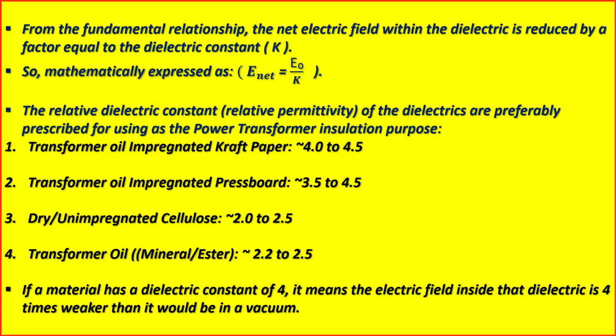It is very essential for designing a power transformer insulation system. Transformer oil impregnated kraft paper: the dielectric constant is 4 to 4.5. Transformer oil impregnated pressboard: 3.5 to 4.5. Dry or unimpregnated cellulose: 2 to 2.5.